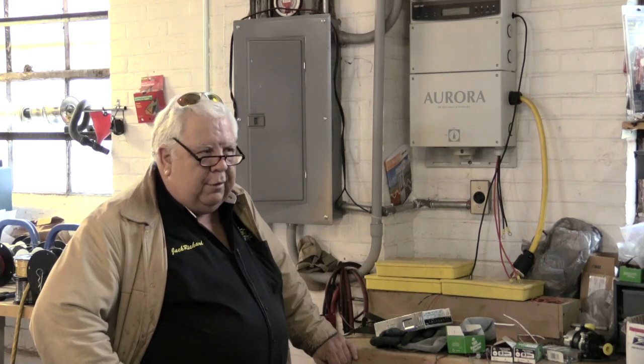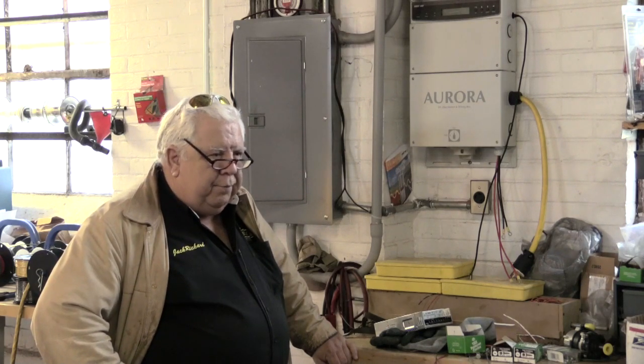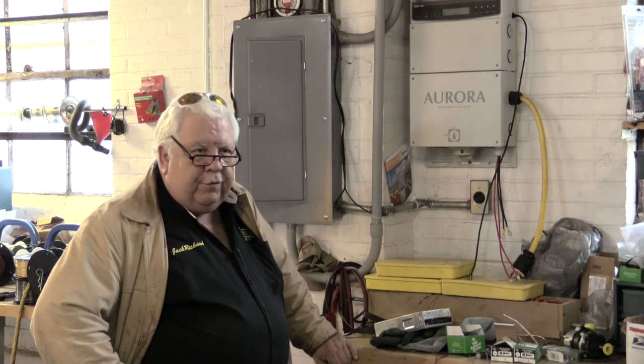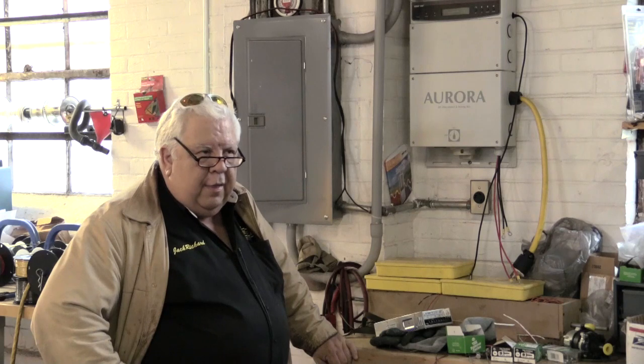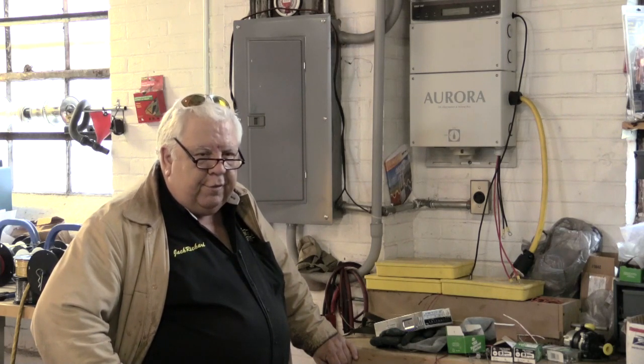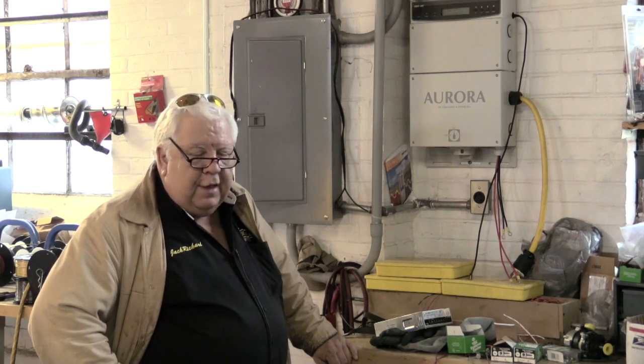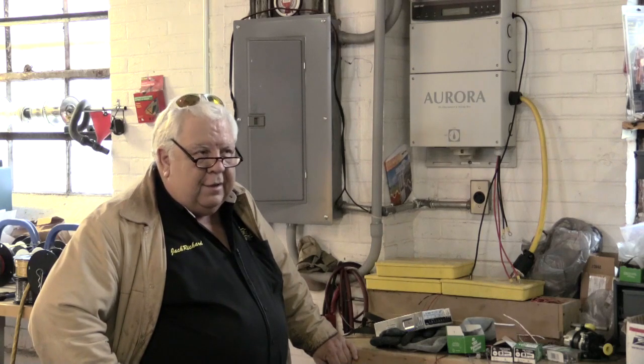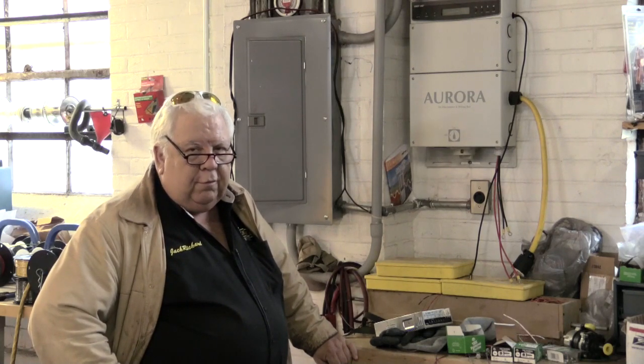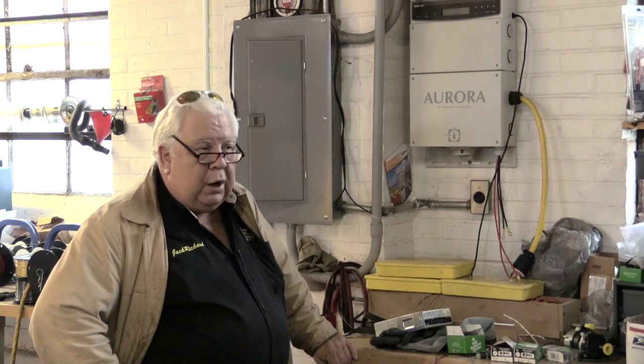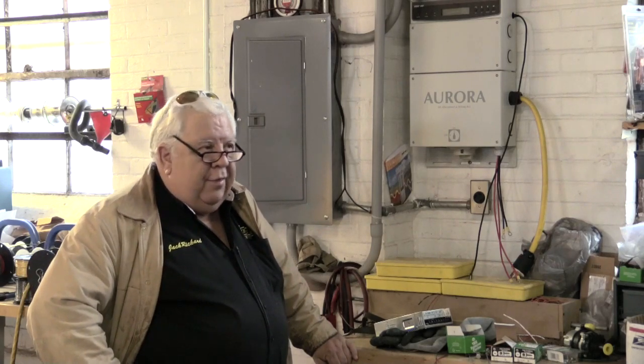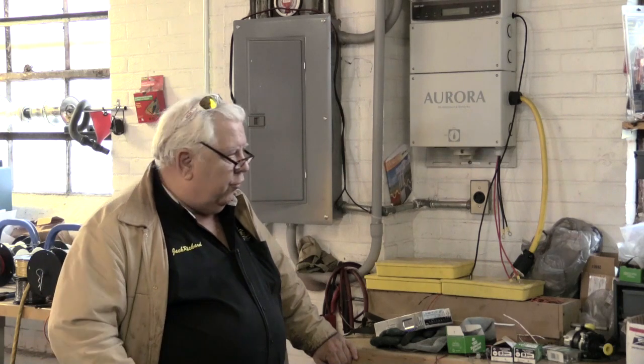Every solar or generator installation I've put in, we've used an automatic service disconnect. It's an AC relay that passes AC from the grid to your system, energized by grid power. If you lose grid power, it de-energizes and connects to your generator or solar system, so there's no possibility of your generator or solar system ever connecting to the grid. If grid power comes back up, it automatically closes that relay, connecting your facility back to the grid. The generator or solar system can be generating power, but it can't contact the grid because this relay has to be in one position or the other.